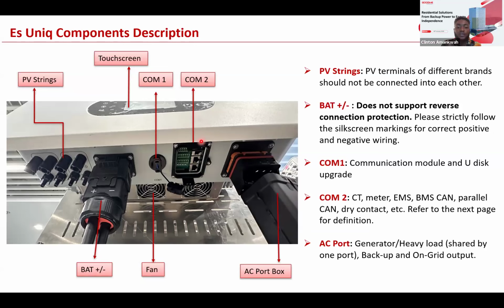So you can make use of this parallel port, or this COM port, to achieve your daisy chain or looping communication between your inverters. And then also connection of your lithium ion BMS cable, as well as CT cable and lead acid temperature sensor cables. Now, the AC port box is where you connect all your AC cabling from your AC input, your AC output, as well as your diesel generator connectivity, should there be the need to connect a diesel generator to your system. Yep, so maybe you can go next.